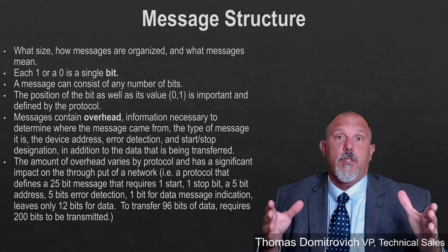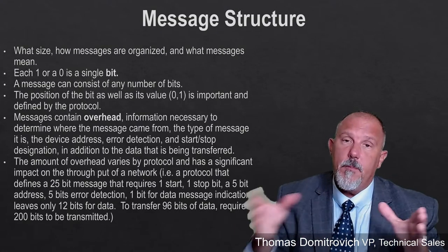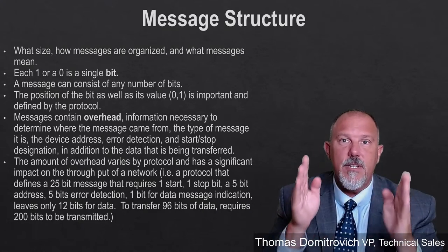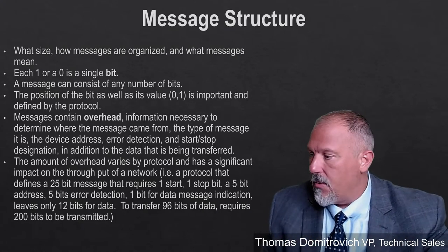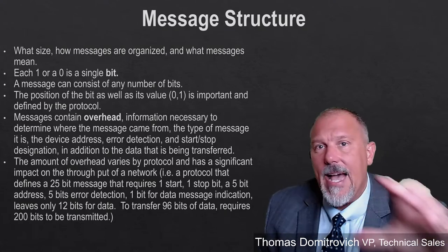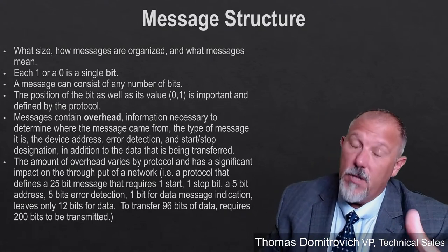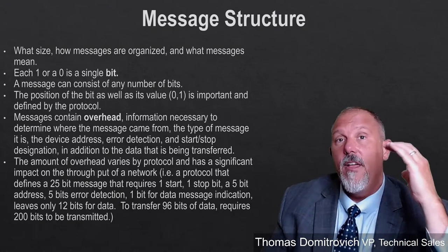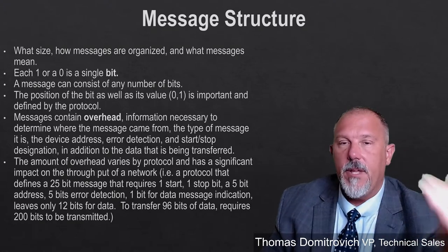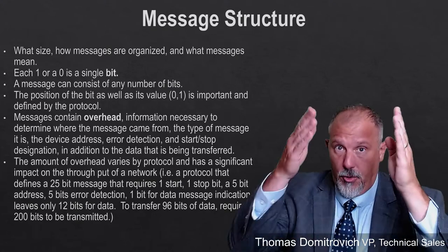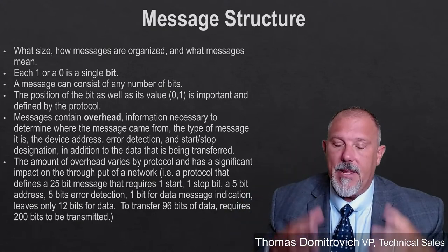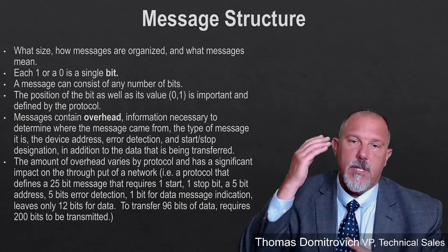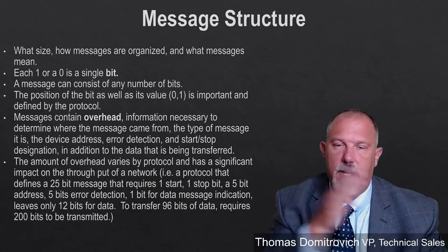Message structure. So here's another thing. Every protocol will tell you what to expect when I send a series of ones and zeros. You might have a program that captures messages. Another really important aspect, if you're trying to troubleshoot, is to have a program that will glean the information off of the network and show you the raw data. That is a troubleshooter's dream, to be able to see the actual messages come back and forth.